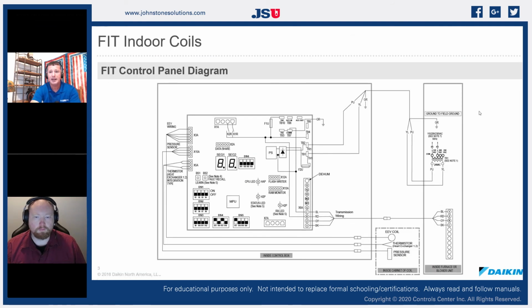If we look at the wiring of that, if we take a look at what's coming from the furnace, we've got a 4-wire connector, a cable that is running over to our EEV, and it's going to have the 24-volt power from the furnace transformer landing on C and R, and then we have our 5-volt communicating on 1 and 2. But when we install this cased coil, we install this separate transformer, and right here is the key to it. The separate cable coming up to the EEV coil has a dedicated ground wire that has to be grounded to the same place that that furnace transformer is grounded.